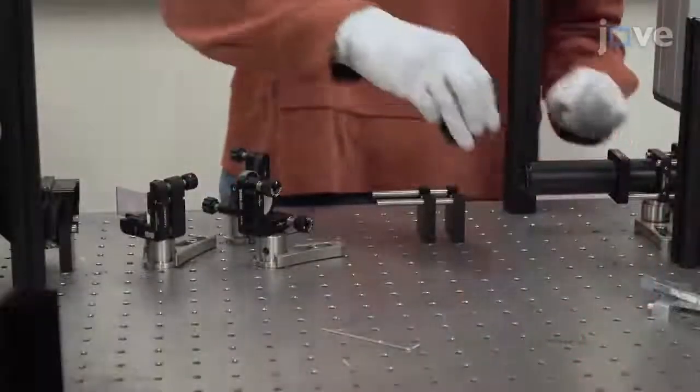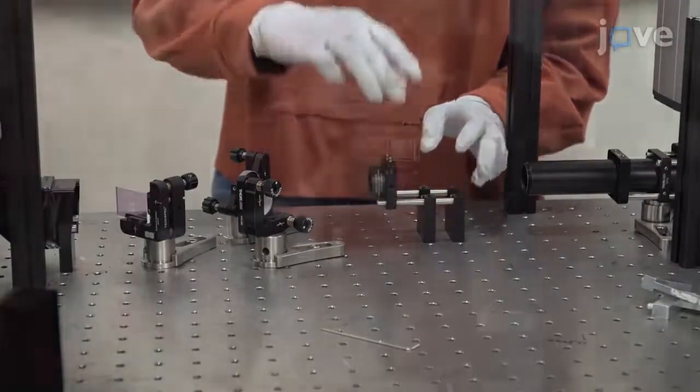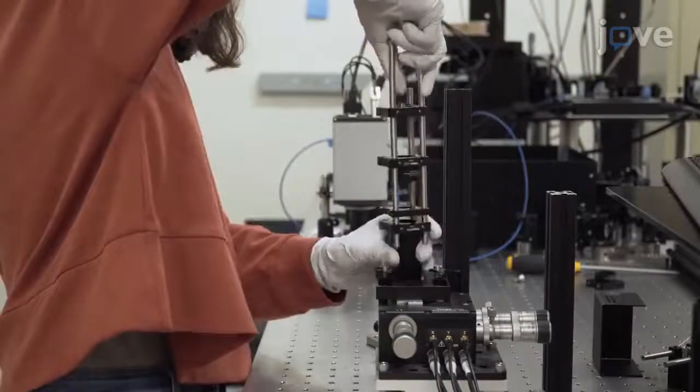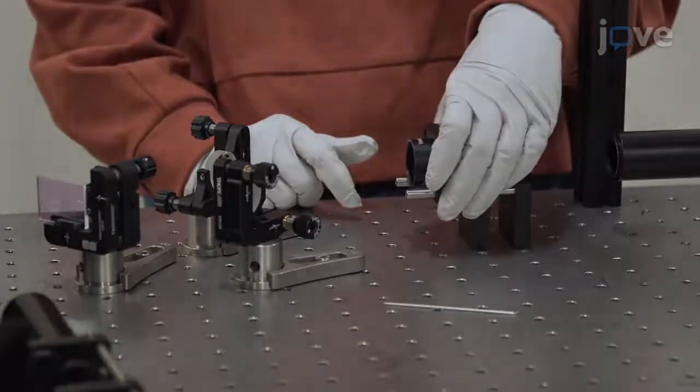Next, insert a 300mm focal length tube lens about a focal length from the camera. Remove the collimated light source from the microscope body. Then adjust the position of the tube lens in order to set its focal plane. Stop the adjustments when the camera...